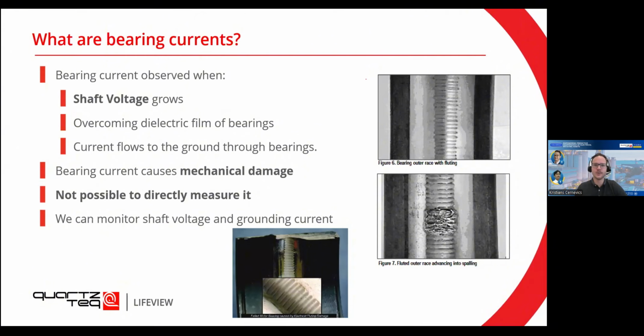As the shaft voltage grows, it will have a charge buildup on the shaft and nowhere for this charge to escape. And for it to escape, it will try to find the path of the least resistance. And what it's going to do, it's going to find it through the bearings. Once it overcomes the dielectric film of the bearings, the current will start to flow through the bearings. And what happens here is that you're going to see real mechanical damage.